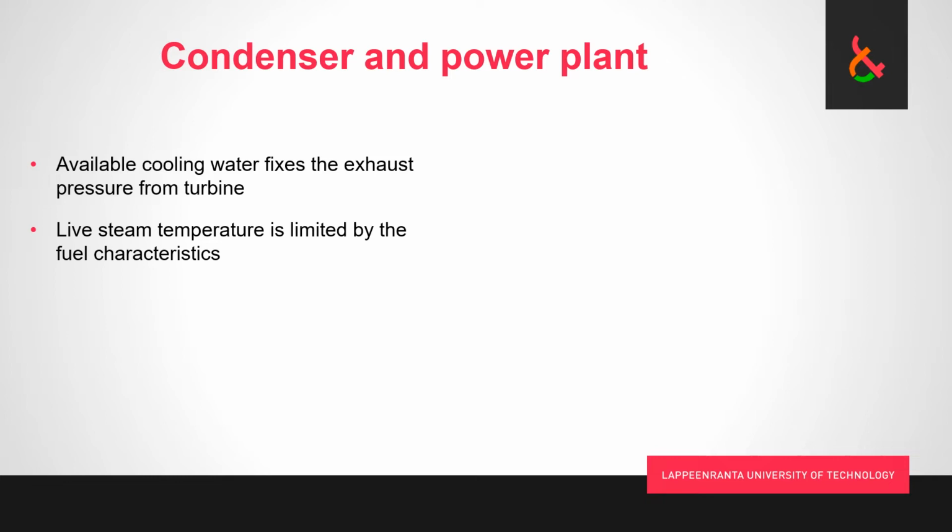That really means that if you want a certain level of steam quality at the end, not too wet so that you would damage the turbine final stages, but also not so dry that you're wasting heat that could be converted to energy, then there's not a whole lot of room left in how you can select the live steam pressure.